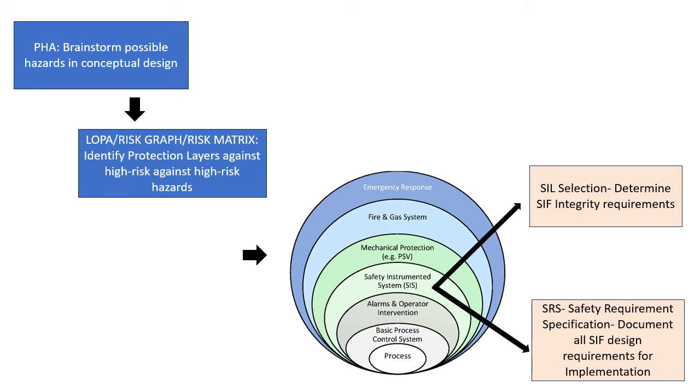What is done in hazard and risk assessment? This is the brainstorming to identify the possible hazards in the conceptual design. This is qualitative, not quantitative. Then there is a quantitative LOPA, risk graph, or risk matrix where protection layers against high risk hazards are identified. This is where the risk gets quantified.